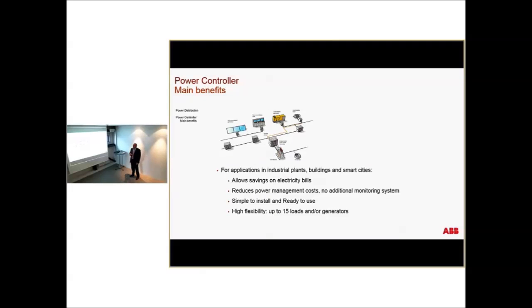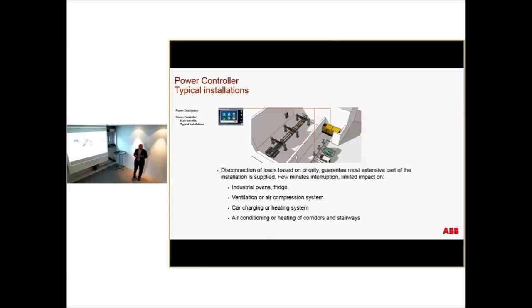Power controller, again, we talk about synchro check, we talk about measurements. Now we have a third device that is embedded inside the release. It is already embedded, you don't need to use a module. And you have the possibility to save on the electricity bill, reduce the power management cost, and manage up to 15 loads. Basically, if you have a load which is not essential, you can decide to disconnect it. You have 4 different times per day when you can disconnect the load. It can go from 1 to 3 hours.